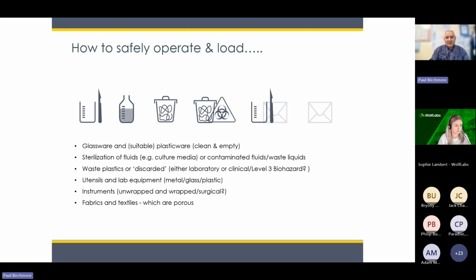So different types of load will be found in the lab, whether it's a university research lab, a medical facility, or any other, a variety of quality control or microbiology labs. And it's considered sterile once it's gone through a full sterilization cycle. Now that is made up of a heating up time, a holding time at the sterilization temperature, and then a cool down phase. So that's what we call the temperature sterilization cycle. But once the load is sterile, you can be confident there are no more live bacteria, live microorganisms that would cause havoc in a sterile environment, such as a lab or a hospital or a food production facility, etc.